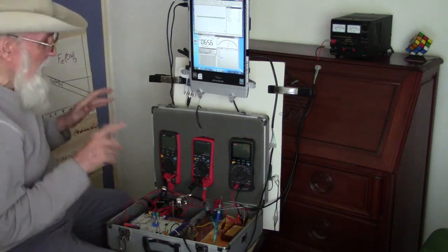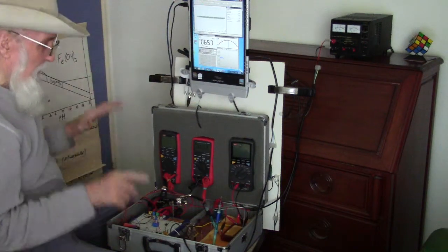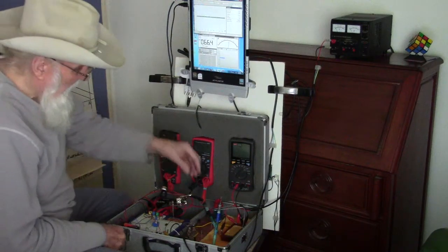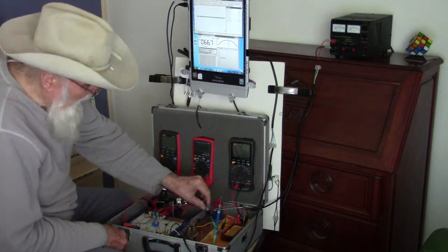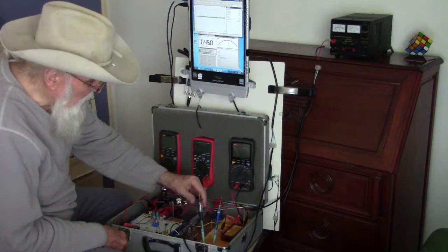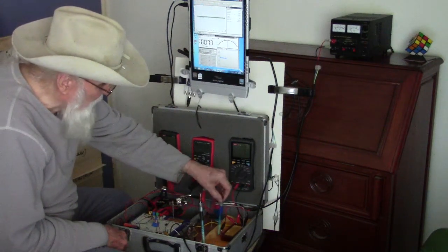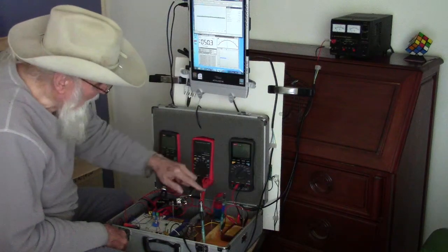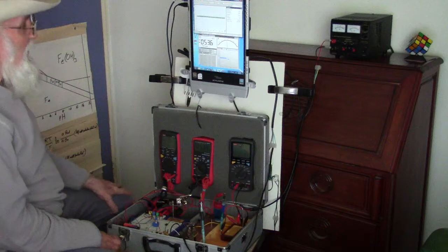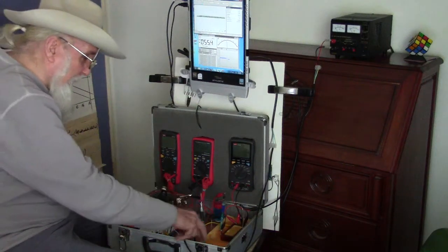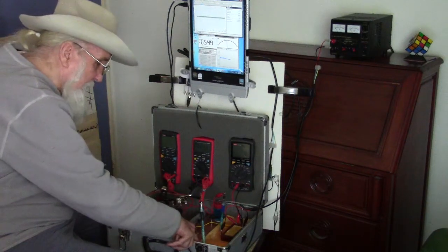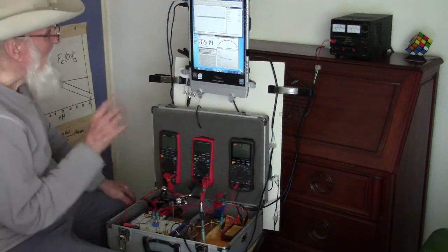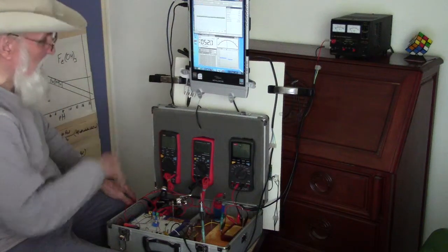This is without the transformer switched on and without the switching. So this is just the setup as found, or some people might call it natural potentials, between this and between that. That means that is the potential difference between the electrolyte at the tip of this and the electrolyte at the tip of that. That's all it means, and that's all we can judge.